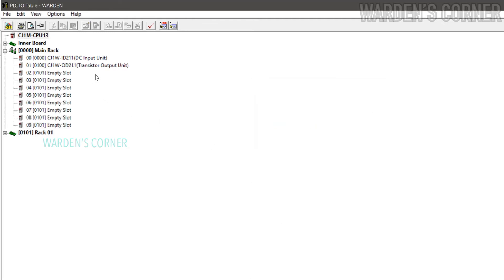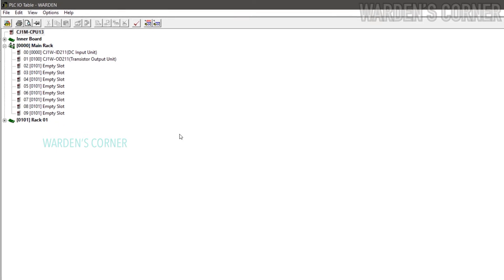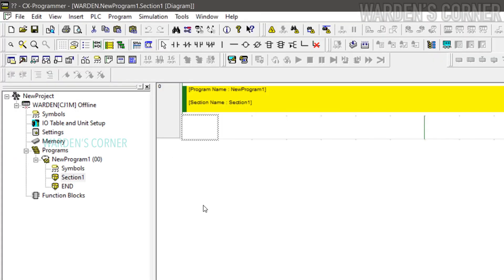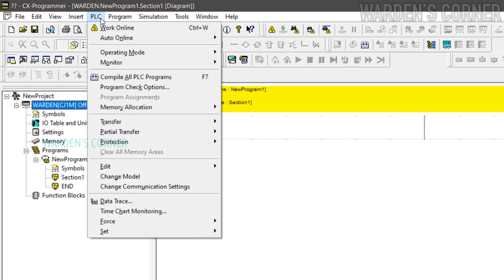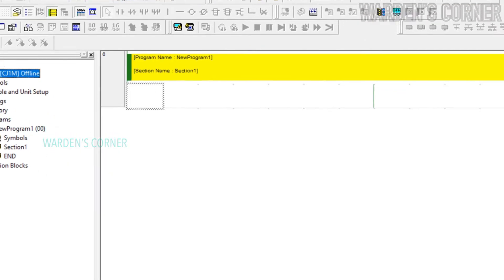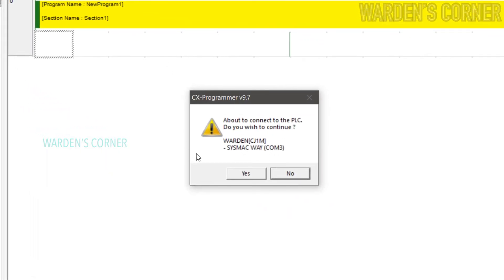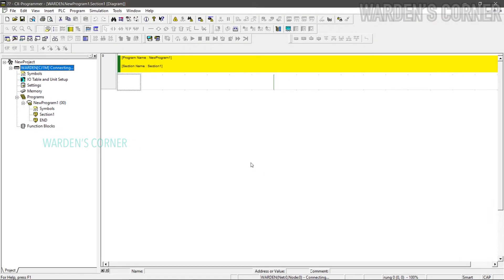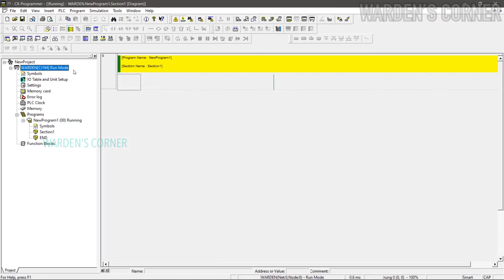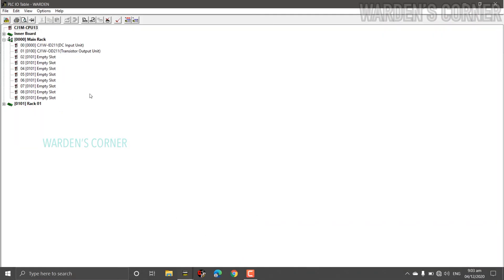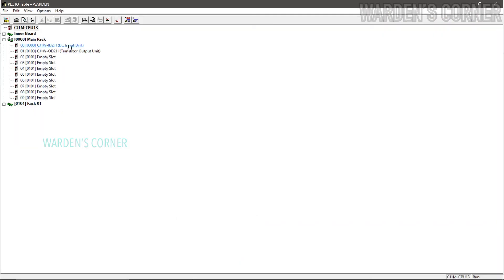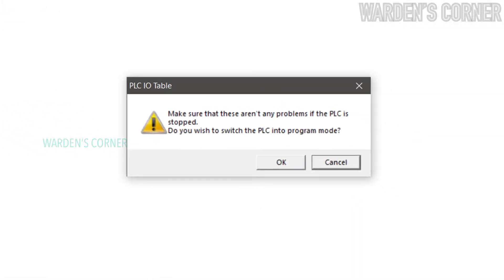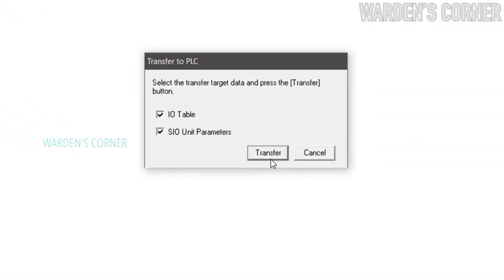How to put I/O Table addresses permanently to our PLC unit. Go to Programming Software Interface. In order to transfer the I/O Table data to the PLC, select PLC from menu area and click Work Online or press Ctrl+W. Connect to the PLC by selecting Yes. The PLC unit is now online and in run mode. Go back to PLC I/O Table tab, click Options and select Transfer to PLC. And click OK.